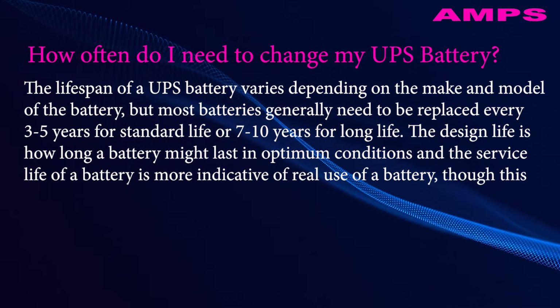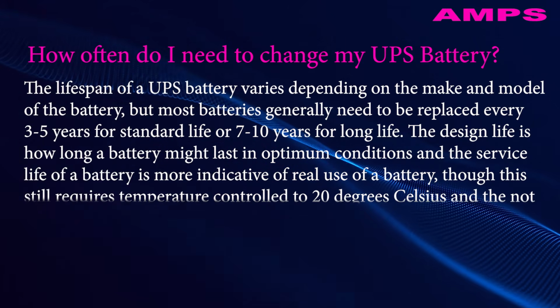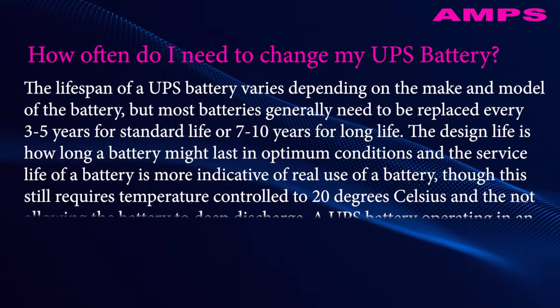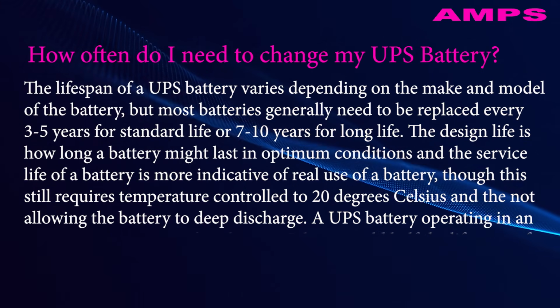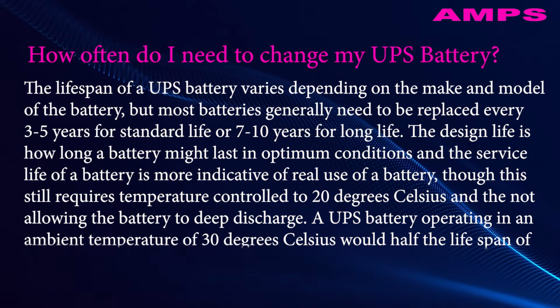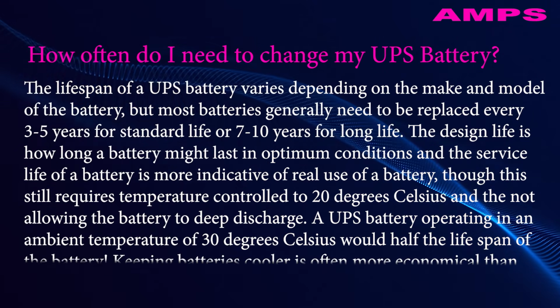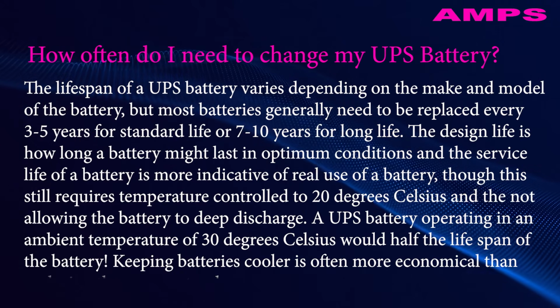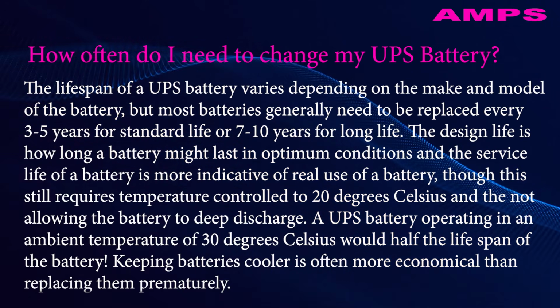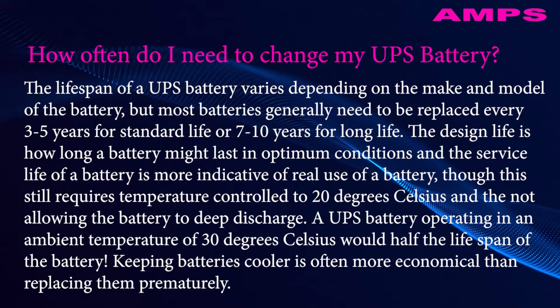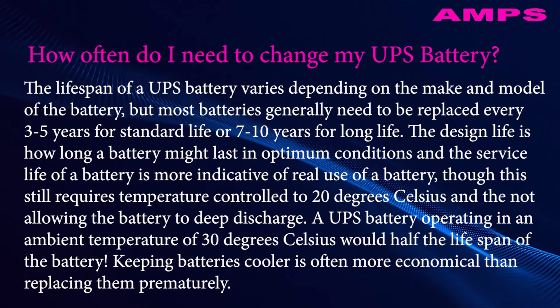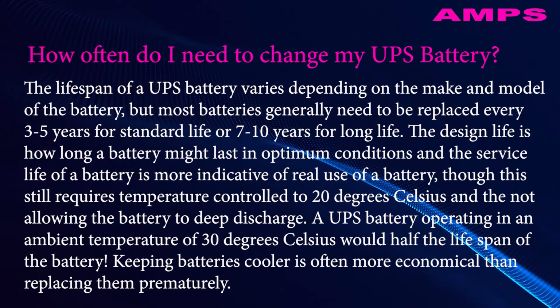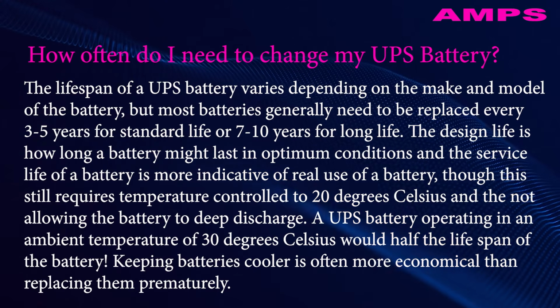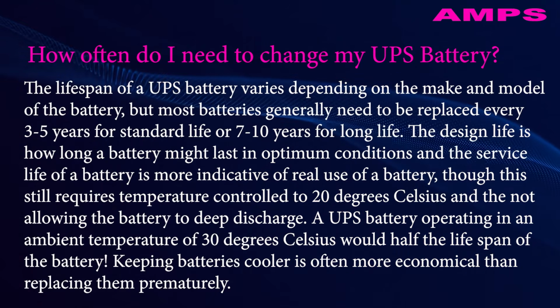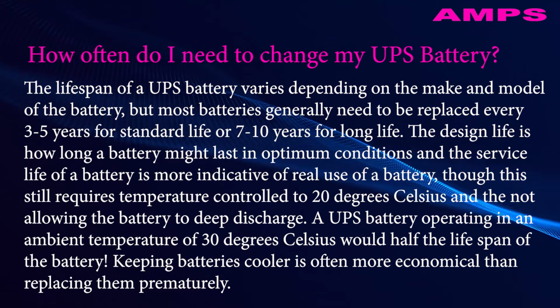The design life is how long a battery might last in optimum conditions, and the service life of a battery is more indicative of real use of a battery, though this still requires temperature control to 20 degrees Celsius and not allowing the battery to deep discharge. A UPS battery operating in an ambient temperature of 30 degrees Celsius would halve the lifespan of the battery. Keeping batteries cooler is often more economical than replacing them prematurely.